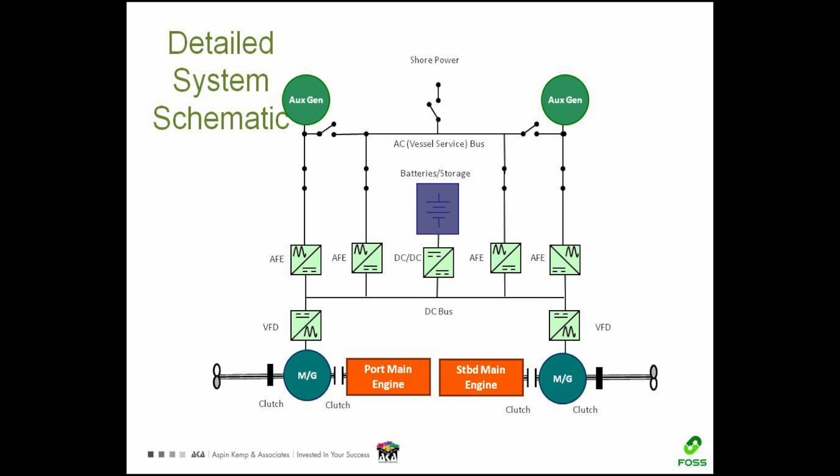So the AFEs are used to support the DC bus and provide power in both directions. VFDs, that term refers to a variable frequency drive. That allows you to take DC power and turn it into AC power to run a normal motor. And the variable frequency means that you can change the speed of that motor. When we did this application for the hybrid system, we had to develop something called an induction generator application, so that this could be an MG set. In generator mode, as an induction generator, this can operate as a variable speed induction generator and also supply power back onto the DC bus.